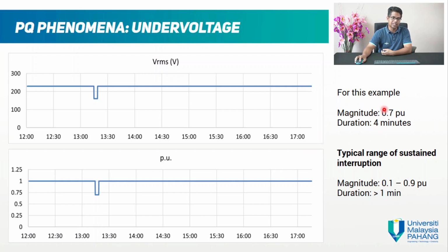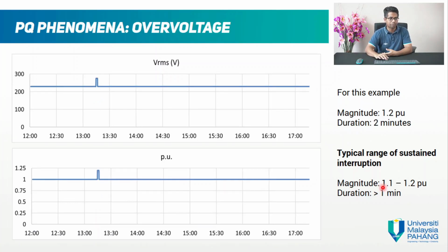This is considered undervoltage because undervoltage is from 0.1 to 0.9 pu when the duration is more than 1 minute. Overvoltage is normally from 1.1 pu up to 1.2 pu. So this is what it looks like if it's 1.2 pu and the duration is 2 minutes.